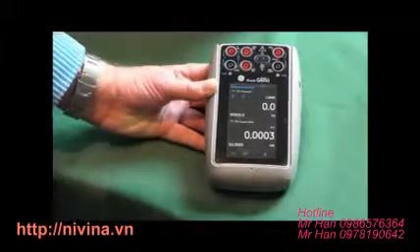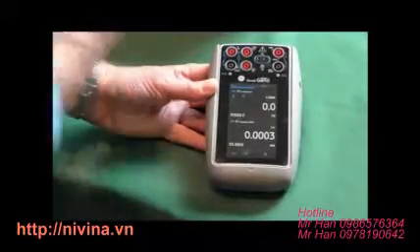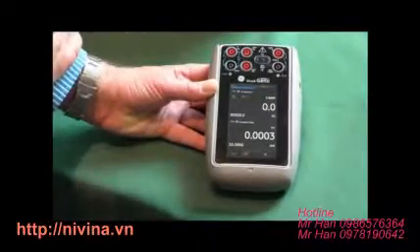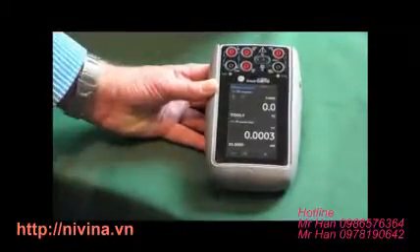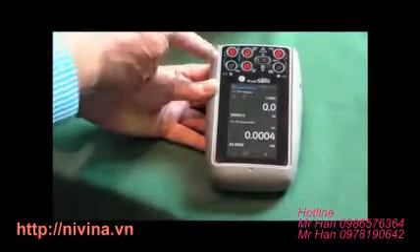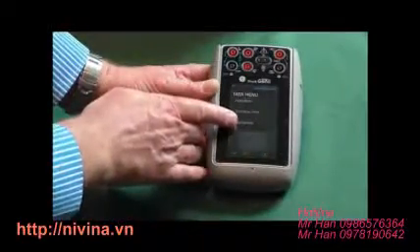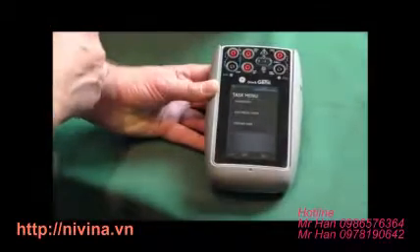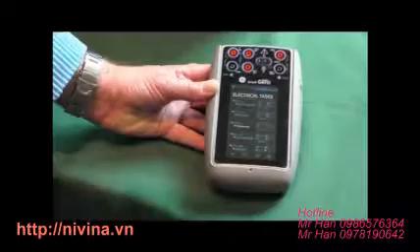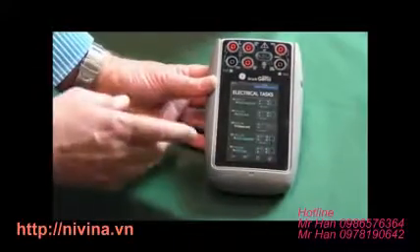So we're working with a transmitter, so what I want to do is power that transmitter from this device. I'm going to provide 24 volts to do that, and as this transmitter's input is an RTD, I want to simulate an RTD on channel 1. I can go into this manually and do what we call a custom task and set that up for each one individually, but we also have our electrical tasks set up in here to make that a lot easier.